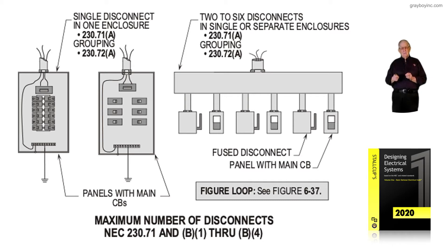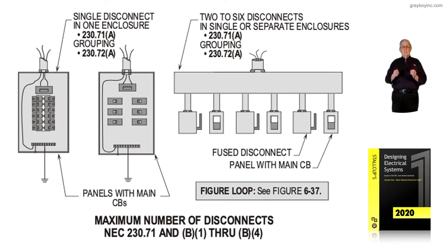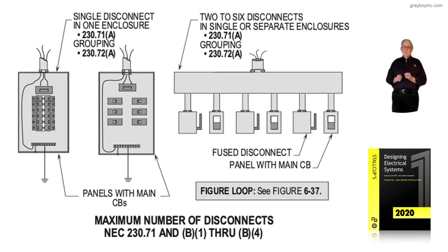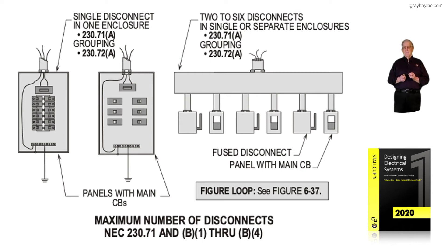The last illustration points out to the right, showing an auxiliary gutter and switches that are tapped there. Look at 230.71A — we're allowed those 2 to 6 disconnects in separate enclosures, but not in one enclosure as you see in the middle. You have to have a main ahead of those, and in 408.36, that permissive rule has been dropped also.